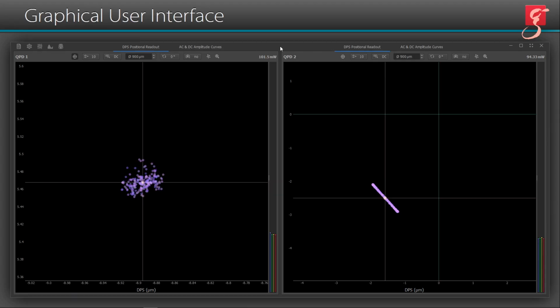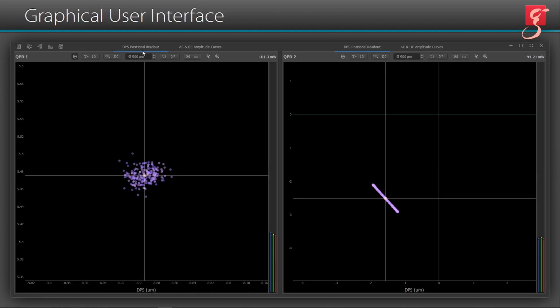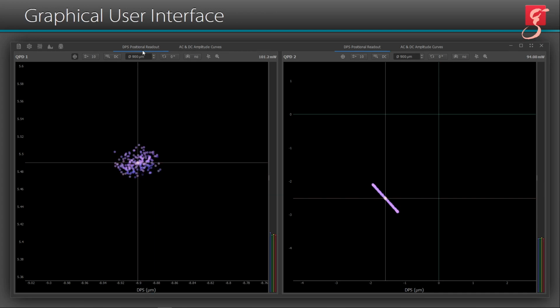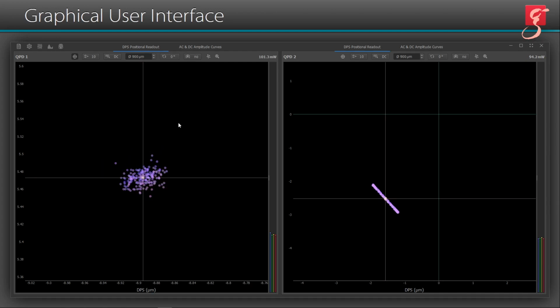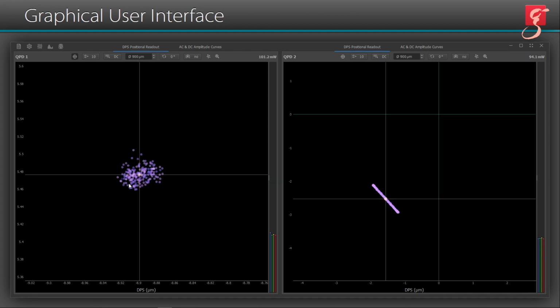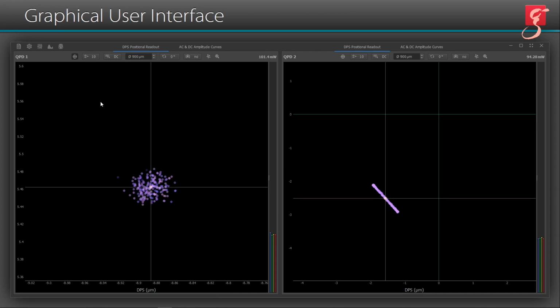The window pane is split into two sections dedicated to QPDs 1 and 2. Each of them has a tab for a positional readout of the laser beam on the QPD, utilizing differential power sensing. The readout is independent of laser power, and its intrinsic nonlinearity is compensated for by an inverse error function, resulting in a true positional readout. A crosshair is displayed to mark the average over a number of individual measurements.